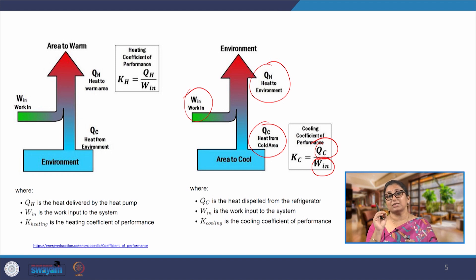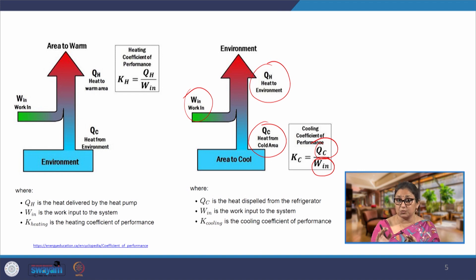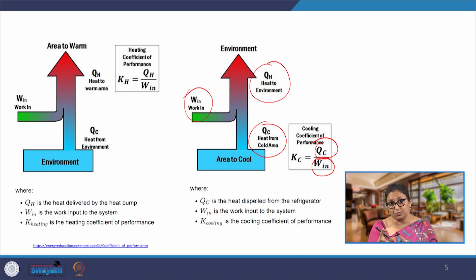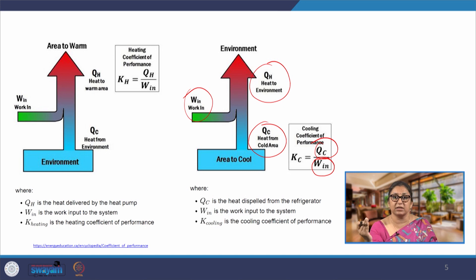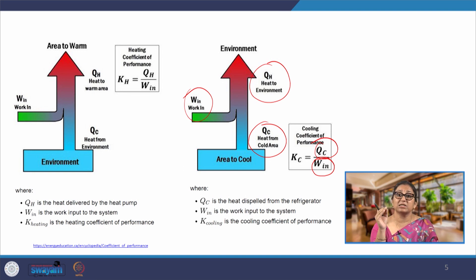The other key concept is the set point temperature. You must have seen advertisements saying to keep the cooling set point higher. If your air conditioner is set at 16°C, it starts working every time the space temperature rises above 16°C, bringing it back down. If you change the set point to 20°C, the air conditioner will not start unless the temperature exceeds 20°C. Raising it further to 24°C means the AC will not start until 24°C is crossed. Changing set points can achieve significant energy saving and efficiency in HVAC use.